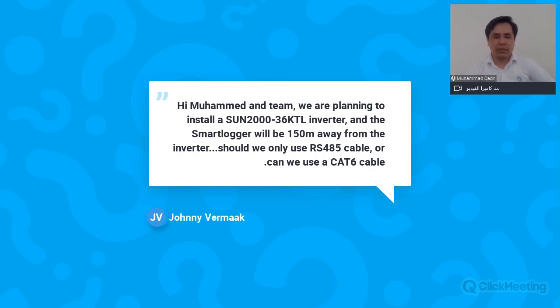Johnny is asking, we are planning to install a SUN2000-36KTL inverter, and the smart logger will be 150 meters away from the inverter. Should we only use RS485 cable, or can we use the Cat6 cable? For this scenario, I recommend you use RS485 cable, because with Cat6, the maximum recommended distance between two nodes is around 100 meters. So with Cat6, you will lose the signal. So please use RS485 cable in this case.